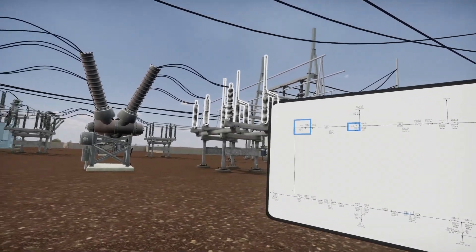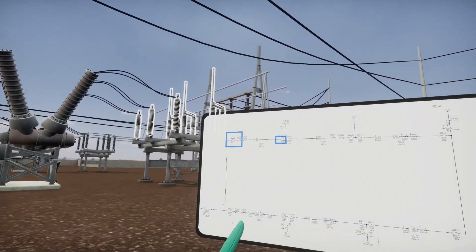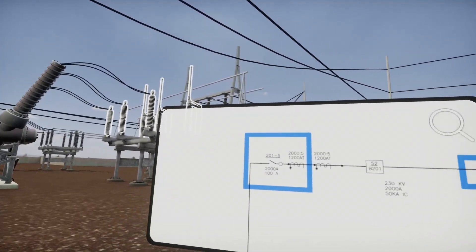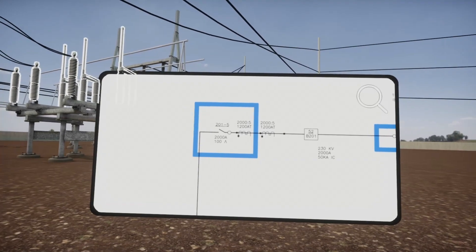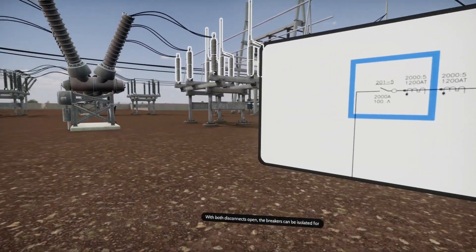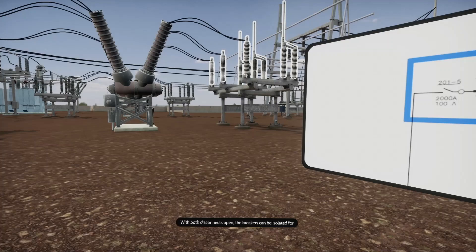Multiple air disconnect switches allow isolation of equipment such as breakers and transformers. With both disconnects open, the breakers can be isolated for maintenance or replacement without de-energizing remaining circuits.